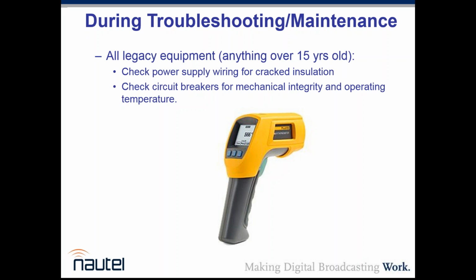Another thing I beat the drum on: you can buy a laser-guided infrared thermometer from Fluke for about $80, and you should check every circuit breaker in your facility. The bulk of the transmitter site fires I run into start in a breaker panel. Copper wires are malleable, and as you compress them in the breaker terminal, they eventually form to fit that, and if you don't have all the air squeezed out, they'll become loose.